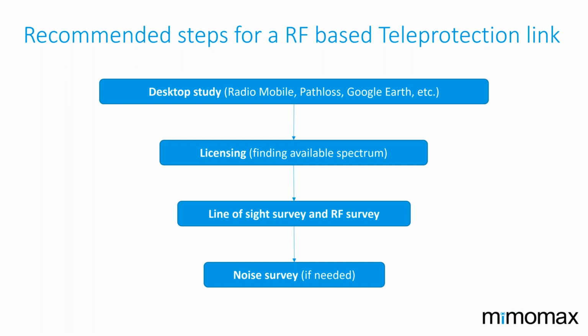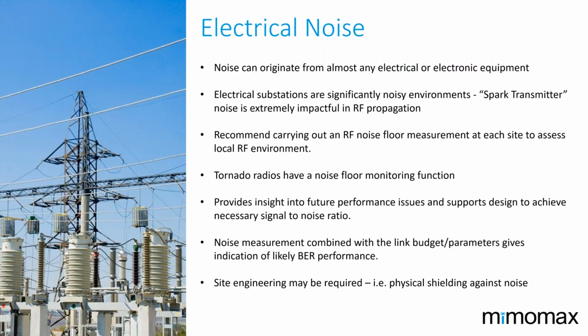One of the big things when considering the type of environments this equipment is going in is electrical noise. Given we're in noisy substations and environments that sometimes aren't conducive to the ideal scenario, we need to be mindful of the spark transmitter or switching transients that happen in these substations. This is a good example of where we'd want to carry out a noise floor test and look at the peaks of those transients. If those transients are hitting significant peaks, they eat into your fade margin and noise margins, and that eats into your availability.